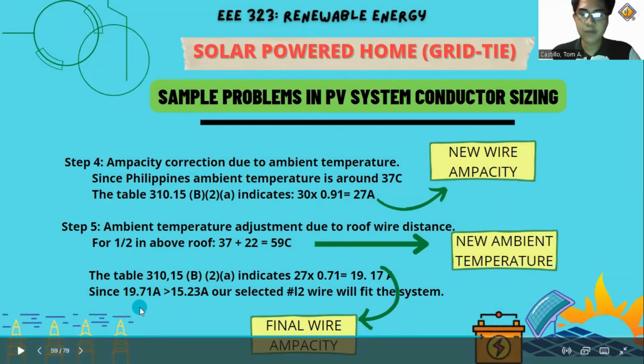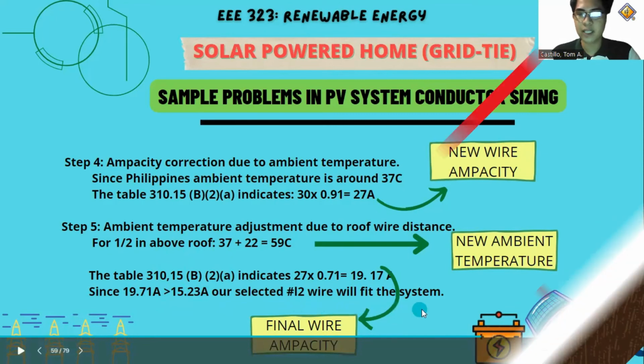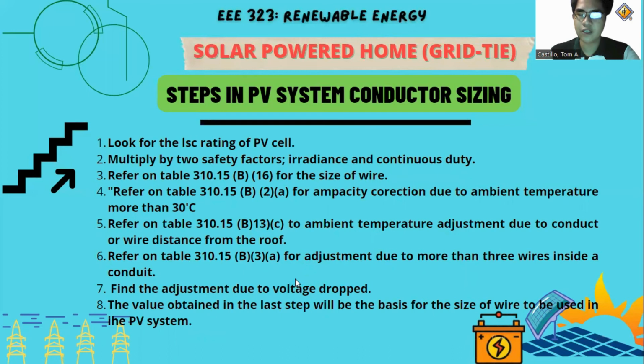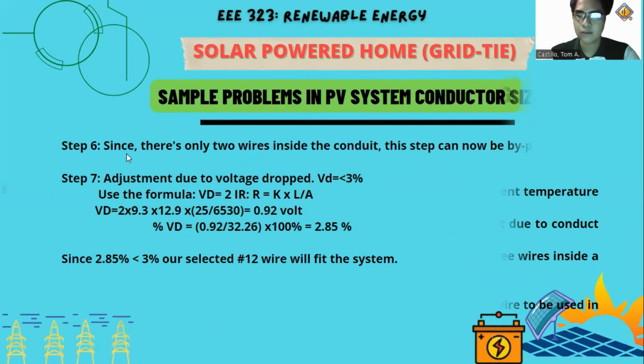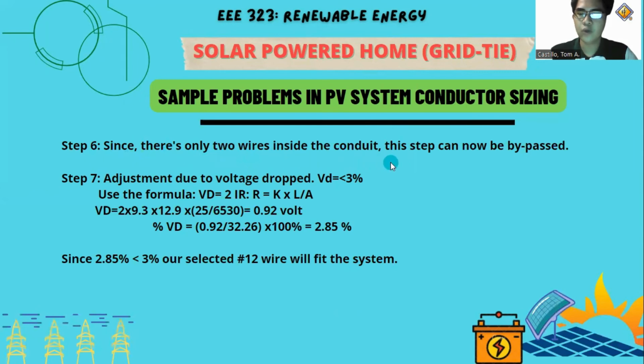So, since 19.17 amperes is greater than 15.23 amperes na original maximum current natin, our selected number 12 wire will fit the system. So, dito tayo sa step 6. Ito yung adjustment due to more than 3 wires inside the conduit. Since there's only 2 wires inside the conduit, this step can now be passed by. So, move na tayo sa step 7. Ito yung adjustment due to voltage drop. So, dapat yung voltage drop natin is less than 3%.